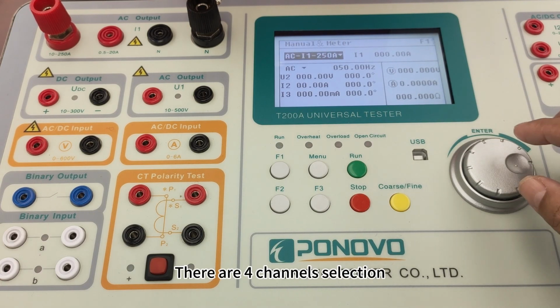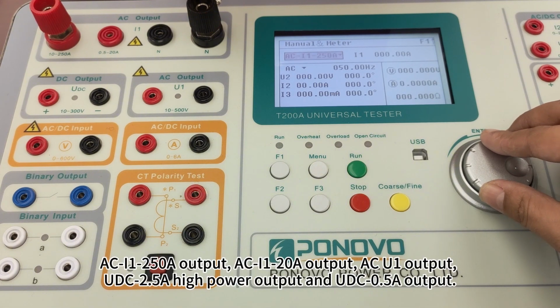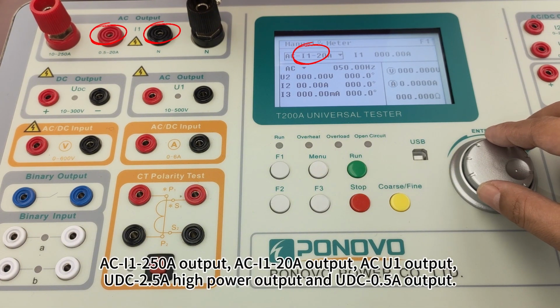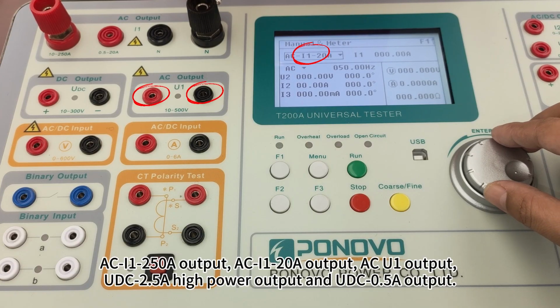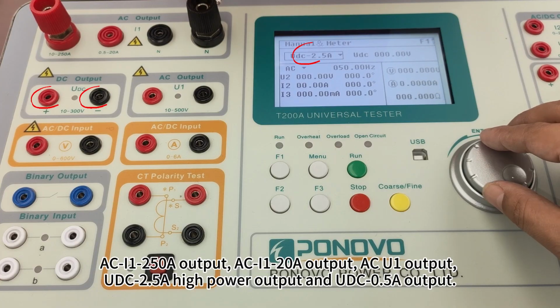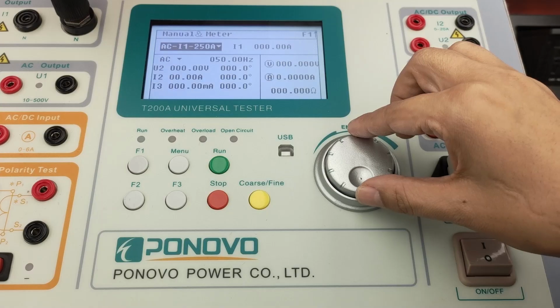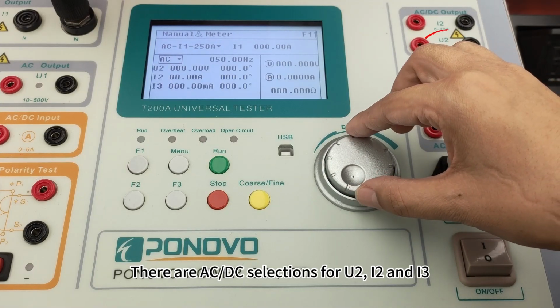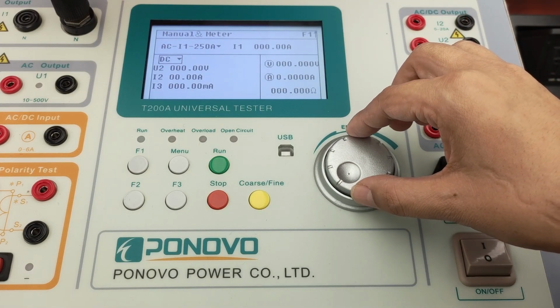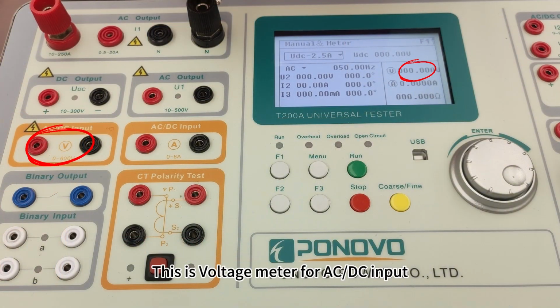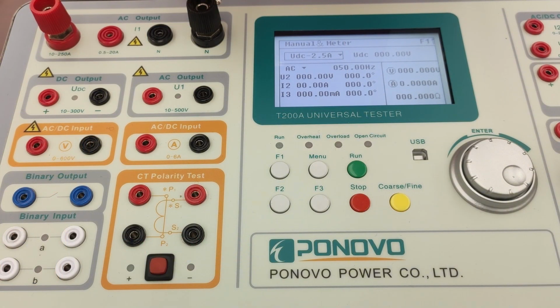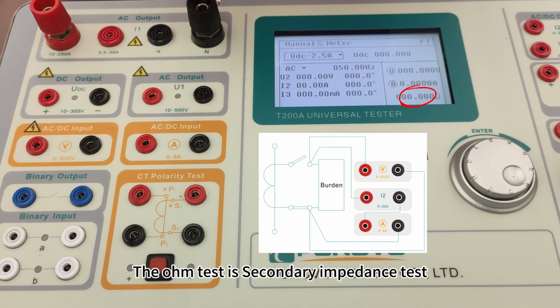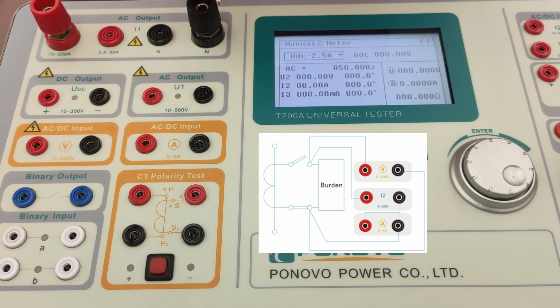There are 4 channels selection. ACI1 250 amperes output, ACI1 20 amperes output, ACU1, UDC 2.5 amperes high power output and UDC 0.5 ampere output. There are AC and DC selections for U2, I2 and I3. This is voltage meter for AC or DC input. This is current meter for AC or DC input. The ohm test is secondary impedance test.